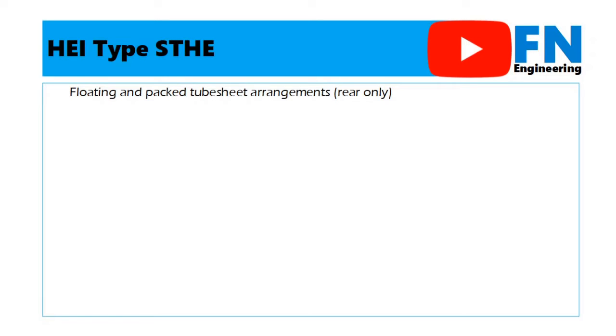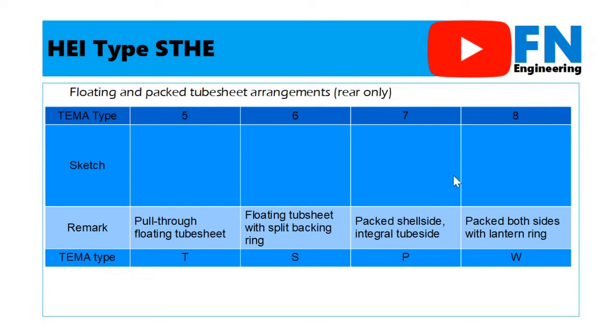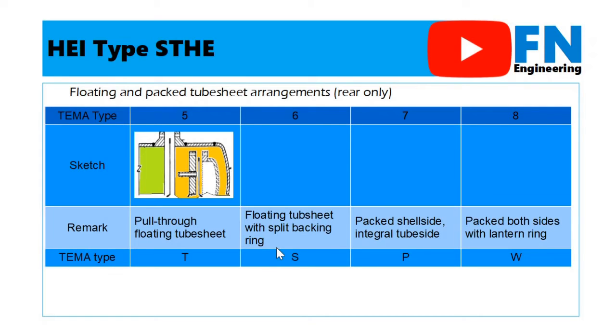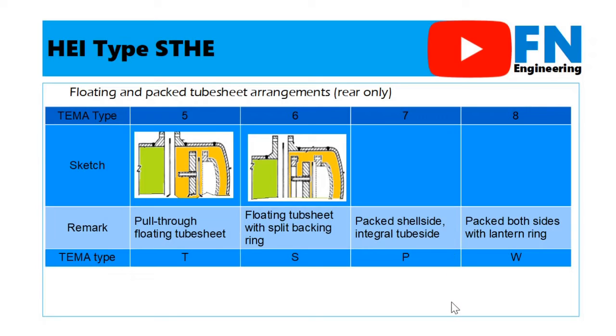The last arrangement is for floating and packed tube sheet. They are for rear head only, including type 5, type 6, type 7, and type 8. These types are also equivalent to the TEMA type in the rear head arrangement. Type 5 is equivalent to type T in the TEMA standard. In this type, the tube bundle can be pulled through including the floating head. The other type is type 6 or type S in the TEMA standard. In this type, the floating head uses a backing ring to prevent leakage between the shell side and the tube side. The next type is type 7 or type P.